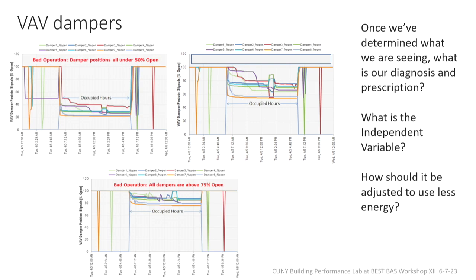So can I ask a question related to that, Michael? Sure. In a lot of systems that are using a supply pressure reset, kind of following the ASHRAE 36 guidelines, trim and respond type activity, I've seen a lot more systems trending exactly like this as the desired point, because they're trying to keep the VAV dampers open to minimize flow restrictions and save fan energy. What do you think on that perspective?